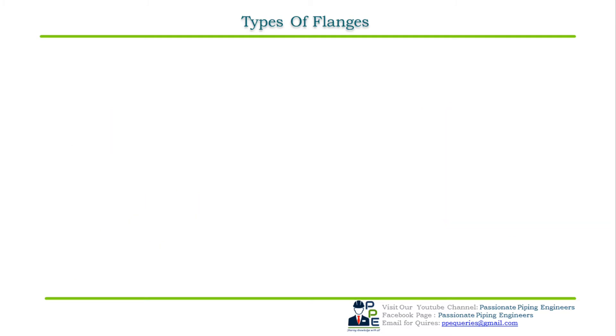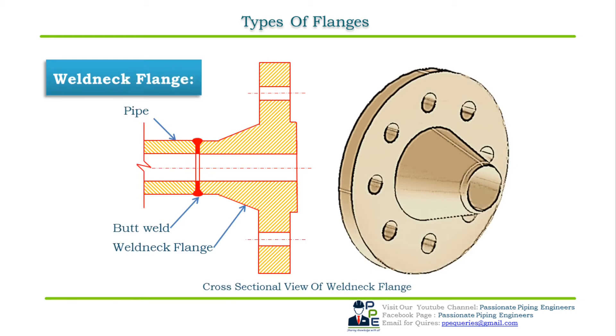The first type is the weld neck flange. A weld neck flange is referred to as a tapered hub flange that can be welded with a pipe or any butt welded or bevel-ended fittings. Weld neck flanges are bored to match the inside diameter of the adjoining pipe. The thicker the pipe wall, the smaller the bore — the inside diameter of the flange is machined to match the pipe ID. The flange NPS and pipe schedule shall match the dimensions of the connecting pipe.